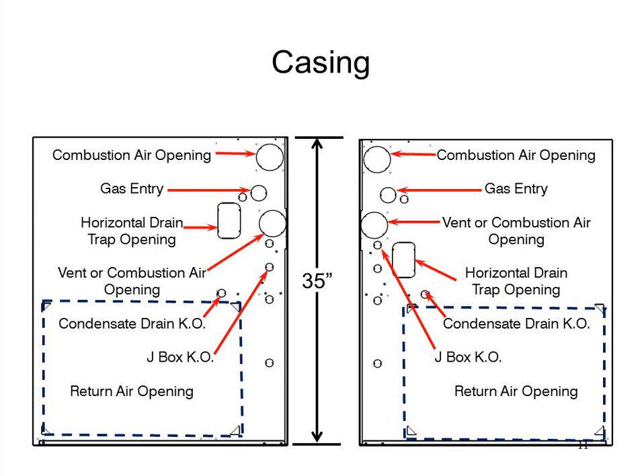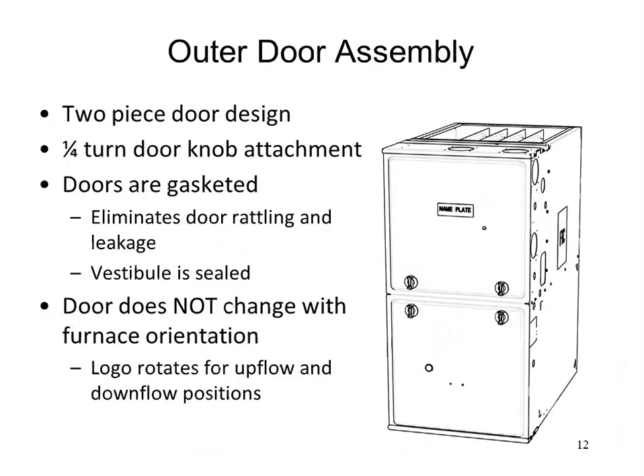These furnaces can be pretty much installed in almost any scenario for replacement purposes. So the combustion air can come in the top of the unit, it can come in the left side or the right side, the gas on the left or right, the condensate drain left or right, the return air left, right, or bottom. So everything's pretty flexible in terms of whatever you're taking out of the system, whatever furnace is coming out versus which one you're putting in.